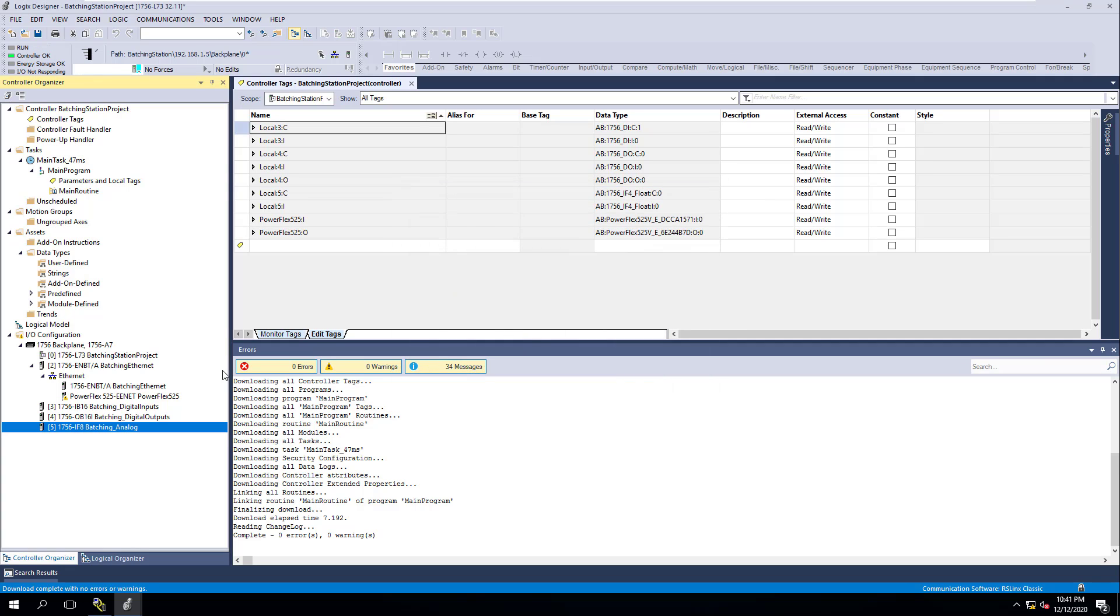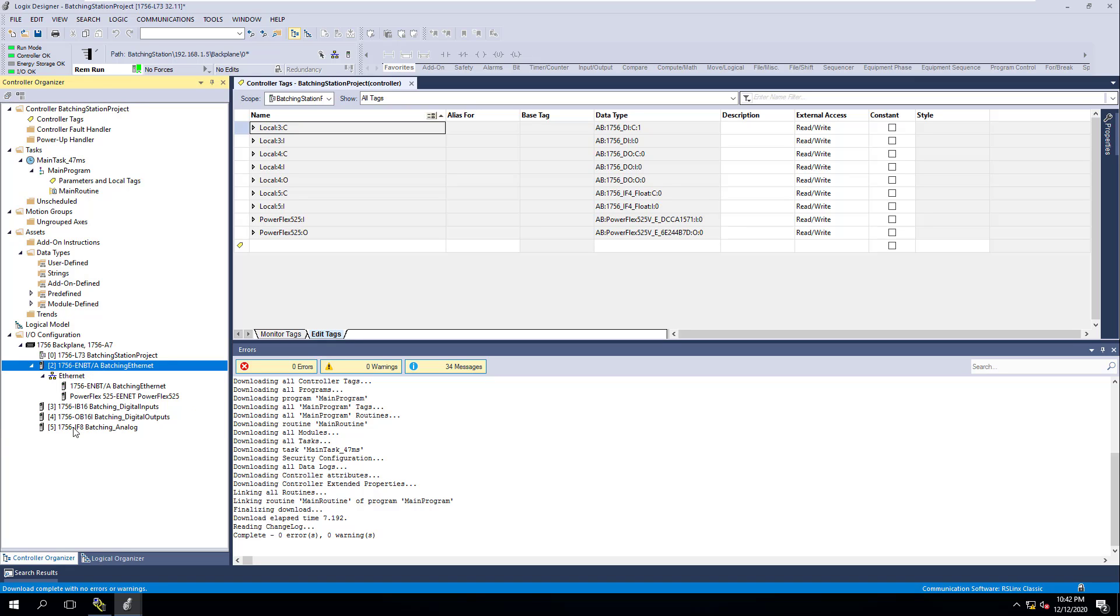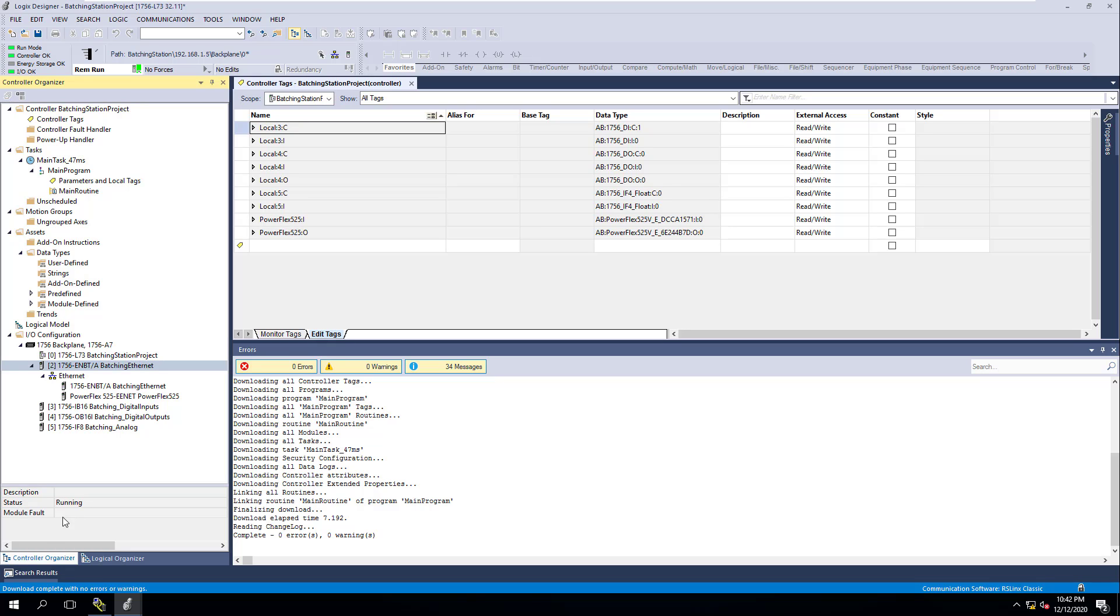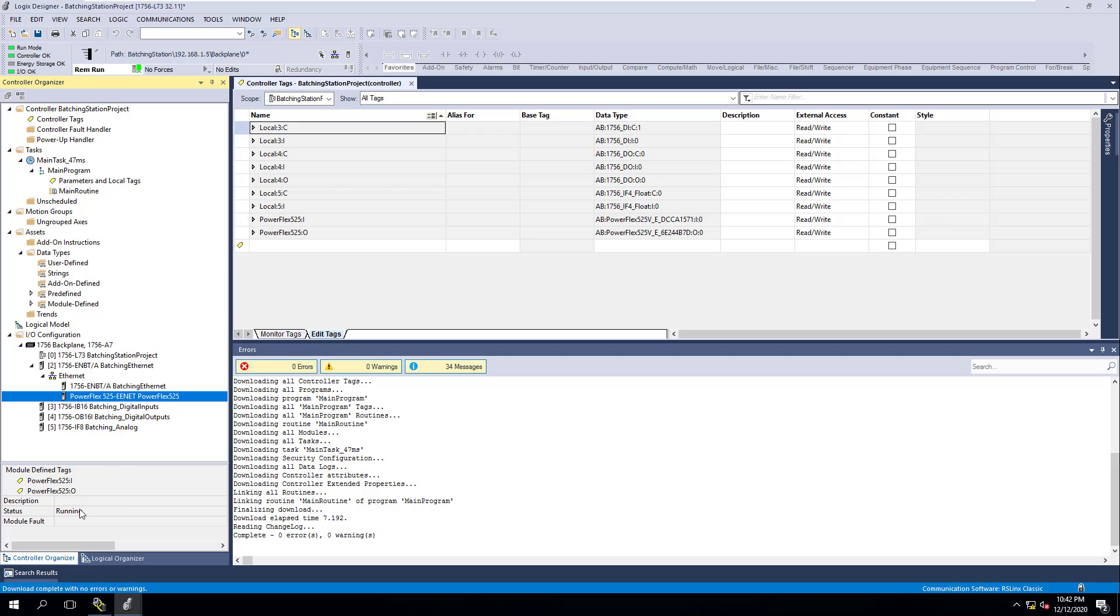This Ethernet device was showing a caution symbol. The caution symbol is going to tell you that it's not communicating or you don't have it set up properly. If you don't have something set up properly, you can come over here and click right here, raise the bottom bar, and see the status of it. See, this says the PowerFlex status right here.